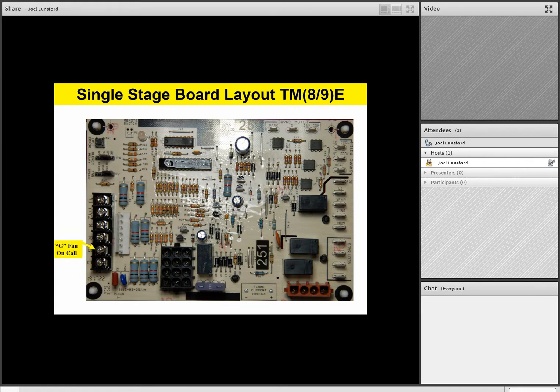The next terminal we're going to talk about is G. That's our fan on call. So when the thermostat calls for fan operation, for instance, in the cooling mode, it will energize the G wire or the G terminal, and it'll bring the fan on. And then we have C for 24 volt common. Now above the low voltage terminal strip, you're going to notice there are some jumpers. Let's talk about those jumpers at this time.